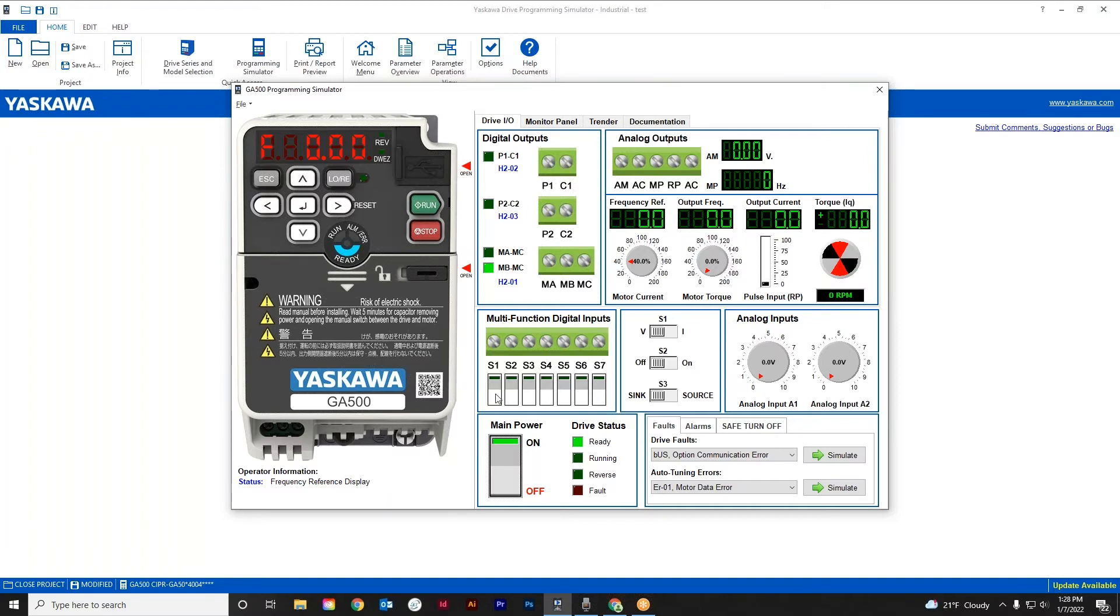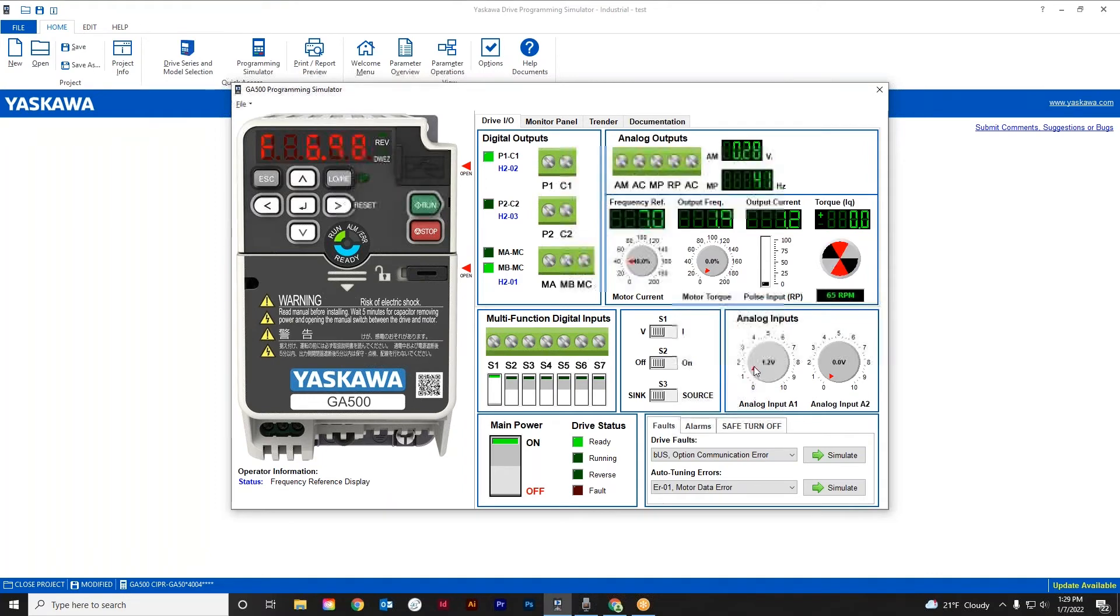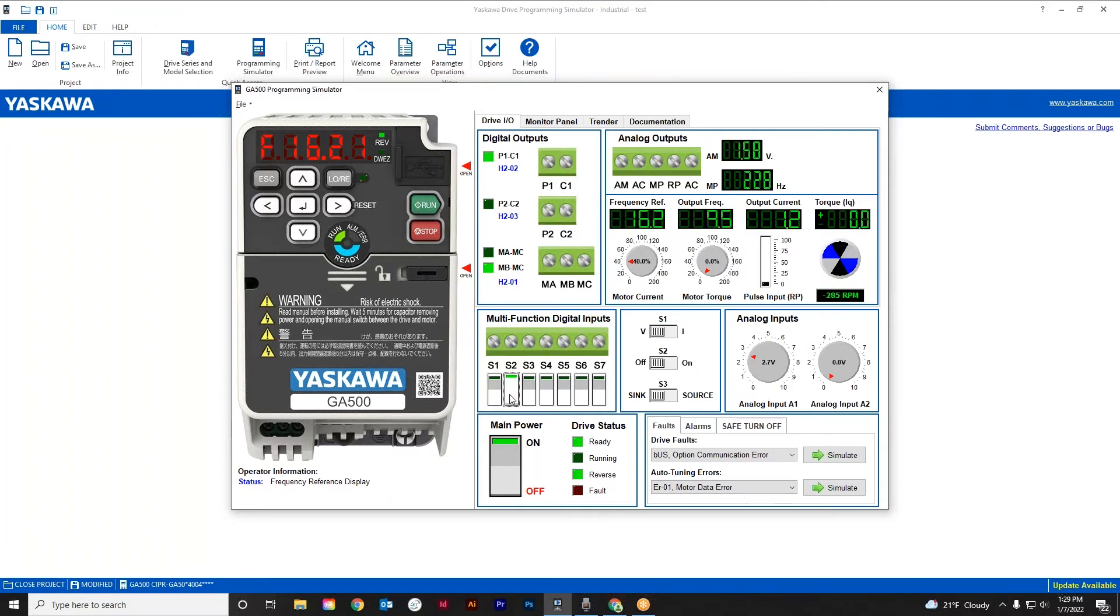Speaking of remote, let's do that. So over here I mentioned that these are the real world connections for bringing your wires in from whatever your start stop buttons or your PLC output or pressure switch or what have you. S1 is your forward input. So if we give it a forward command, we'll see that actually the run light is on, but it's not running. It's not doing anything until we actually give it an analog input. That's what this is over here. So we give a little bit of analog input and we have our motor spin, which is very nice. And if you want it to reverse, then we would do S2. These, of course, are the default settings for these S parameters.